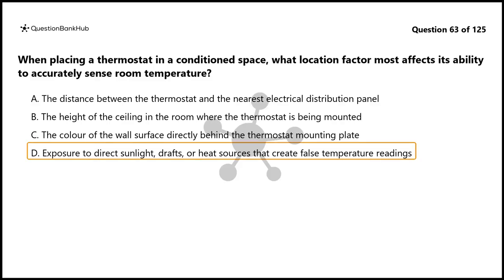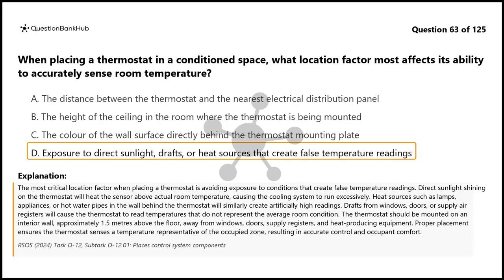The correct answer is D. The most critical location factor when placing a thermostat is avoiding exposure to conditions that create false temperature readings. Direct sunlight shining on the thermostat will heat the sensor above actual room temperature, causing the cooling system to run excessively. Heat sources such as lamps, appliances, or hot water pipes in the wall behind the thermostat will similarly create artificially high readings. Drafts from windows, doors, or supply air registers will cause the thermostat to read temperatures that do not represent the average room condition.